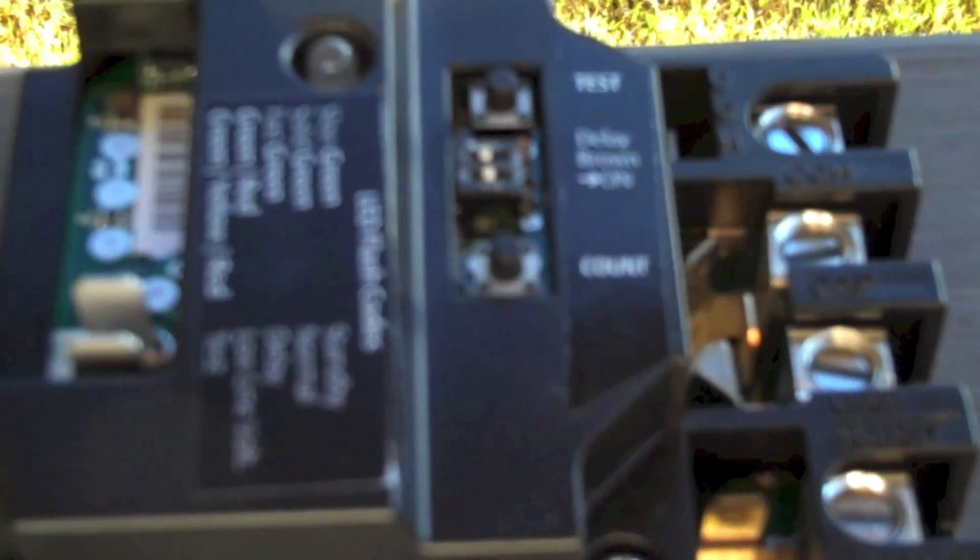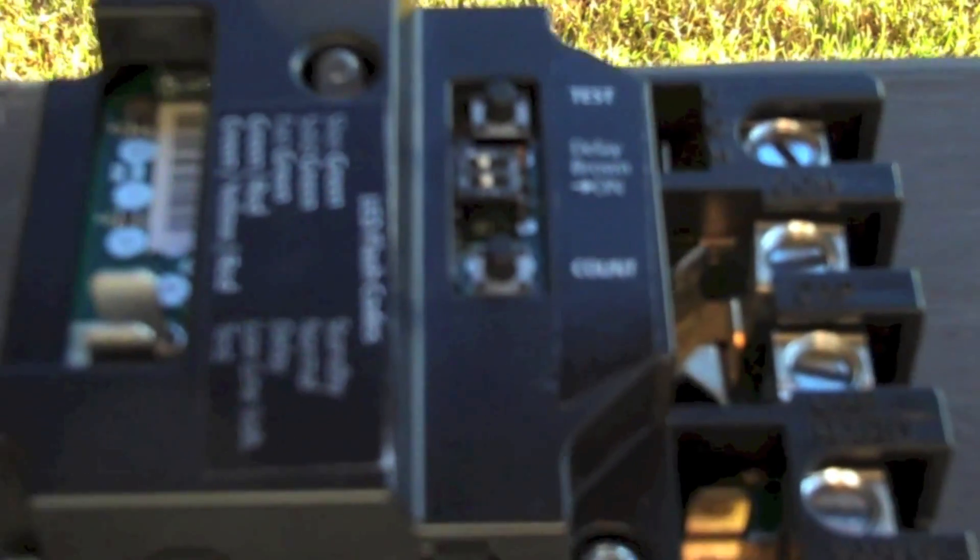The Sure Switch also has a zero-chatter latching relay, which is kind of cool. So there's no holding voltage needed on the Sure Switch, kind of like on a regular contactor which has a holding voltage. These actually consume a lot of power for 24 volts - these are actually power hogs.